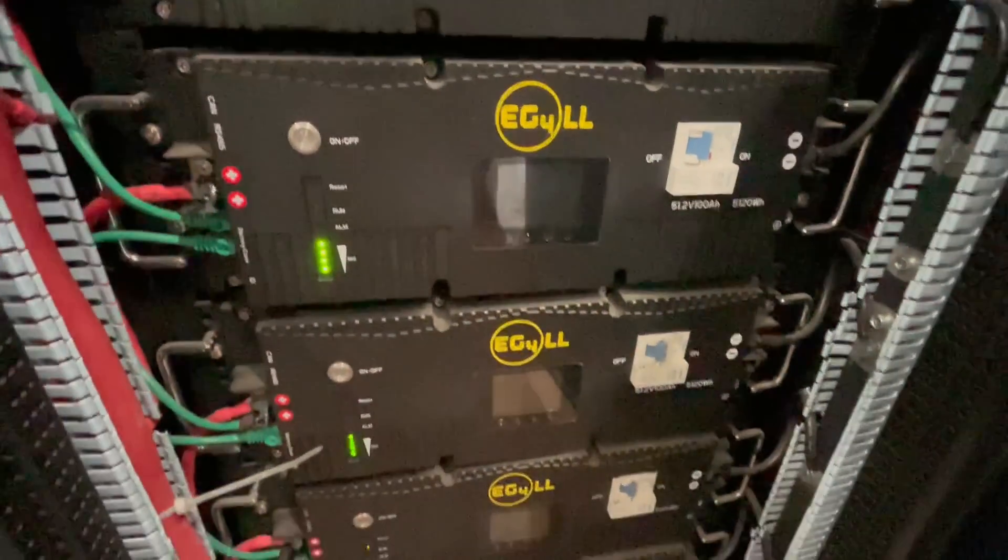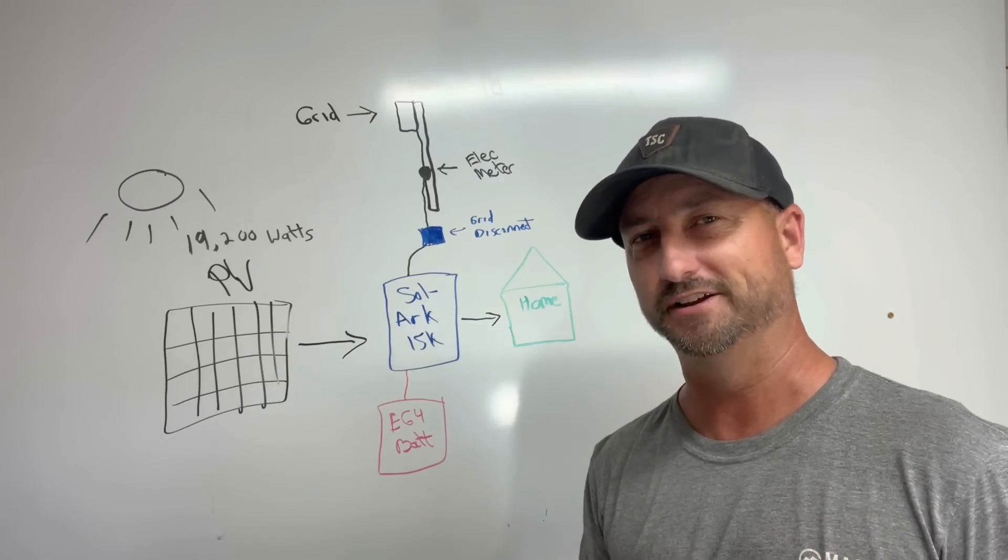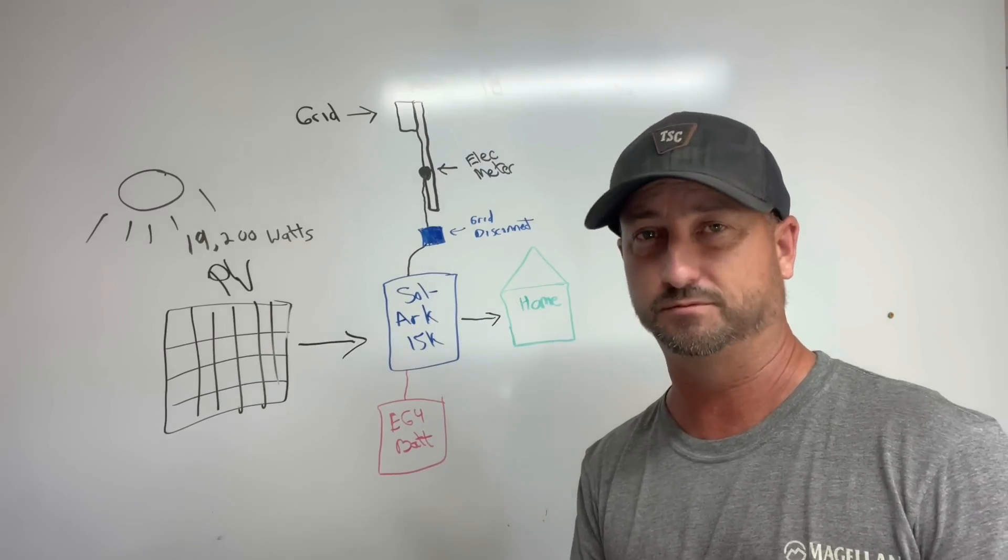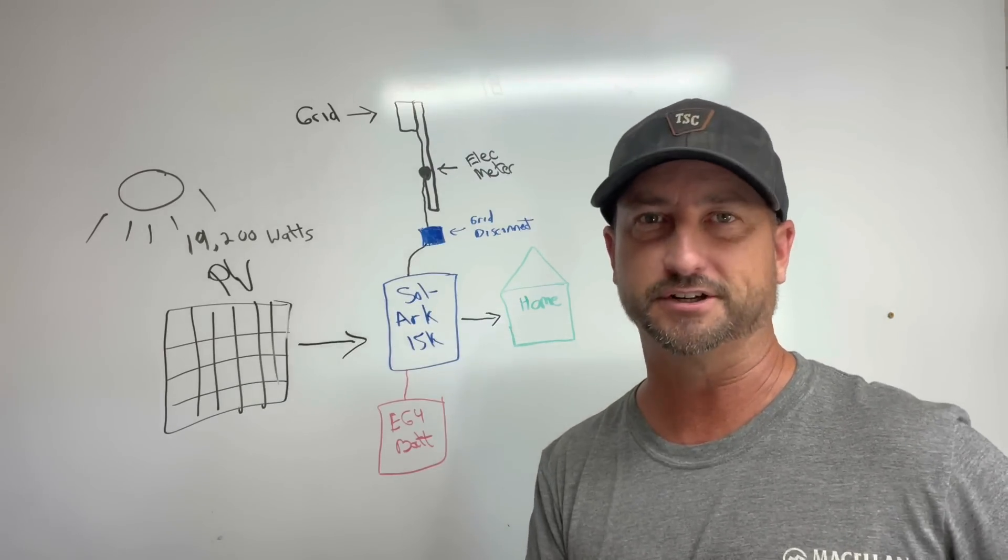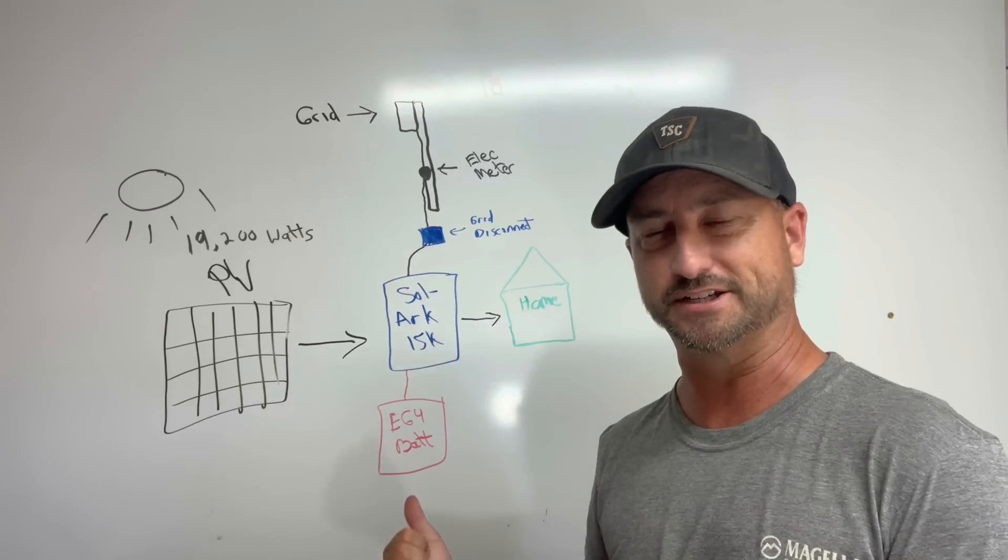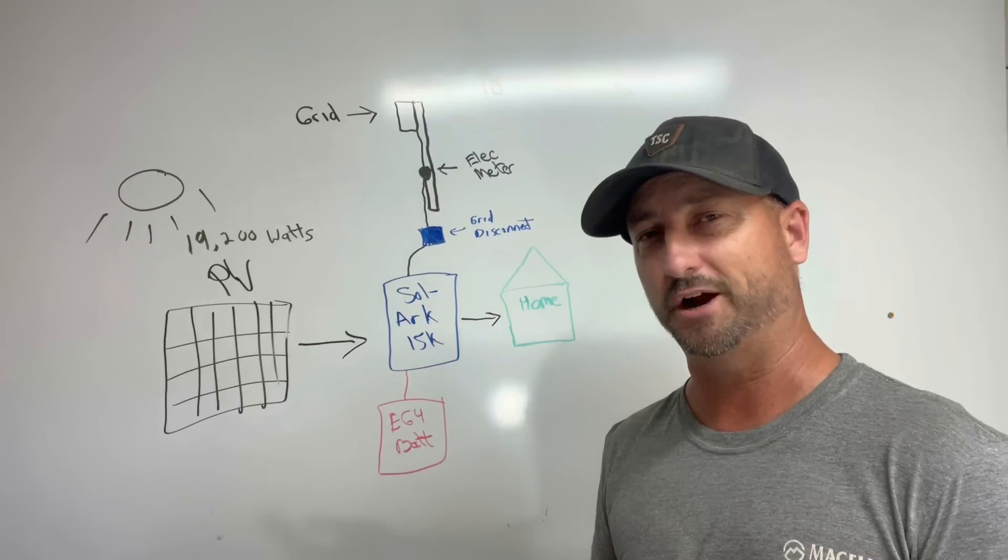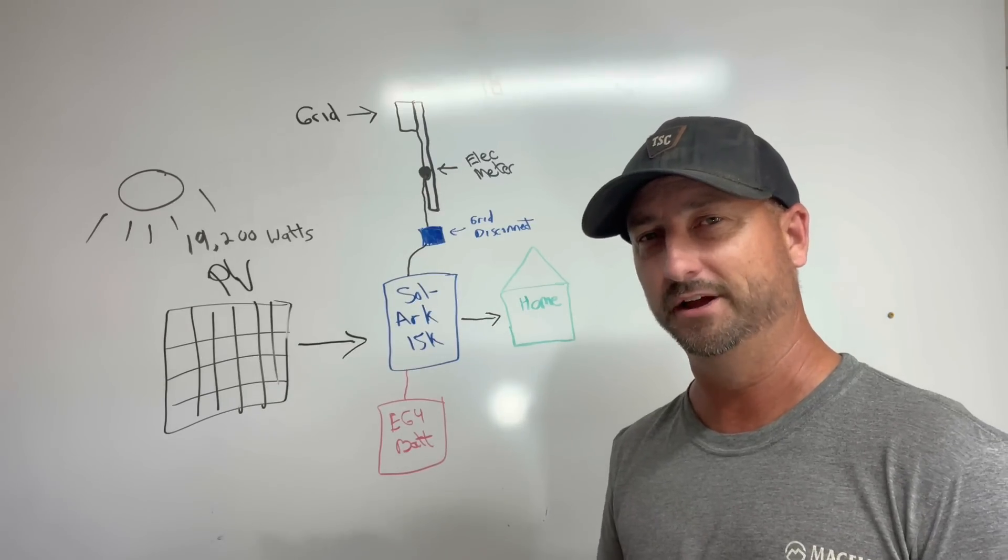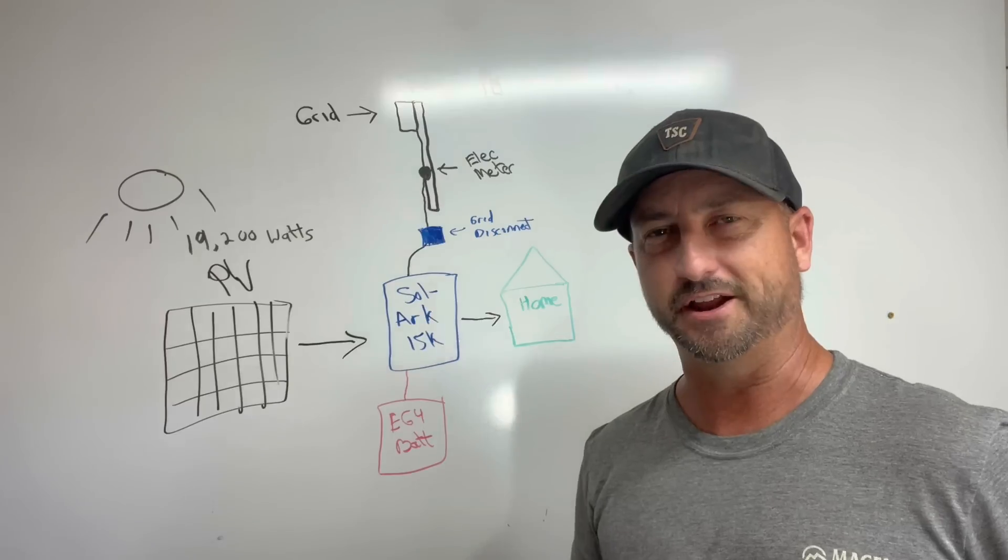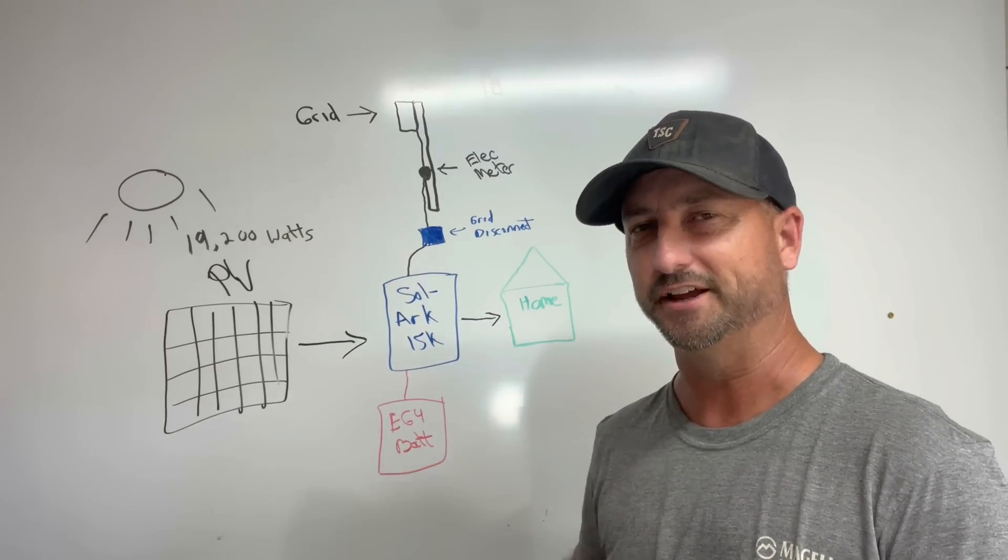So I have it set, which is one great thing about the Sol-Ark 15K, is when your batteries get below 20% it will automatically take from the grid only what it needs to run your loads if you tell it to, or you can tell it to charge the batteries if you want to. But I don't want to do that. I want to save as much money as possible to pay back all the money I spent on this system. So once it gets down to 20% it'll automatically go back to grid just to power the loads for a short period of time until the sun comes up the next day and then it all goes back to off grid again.